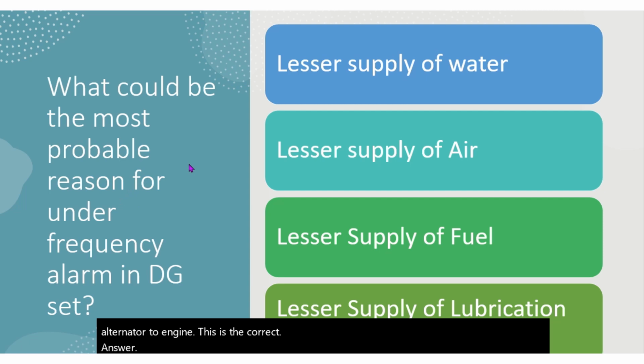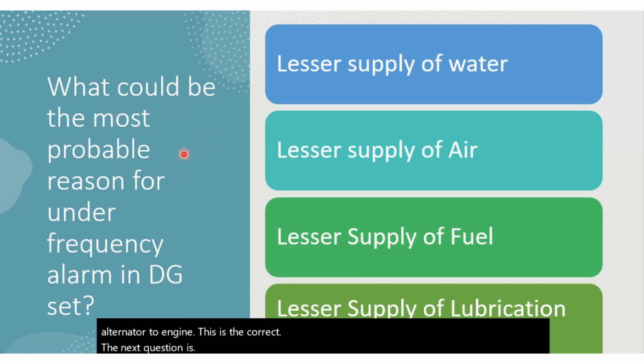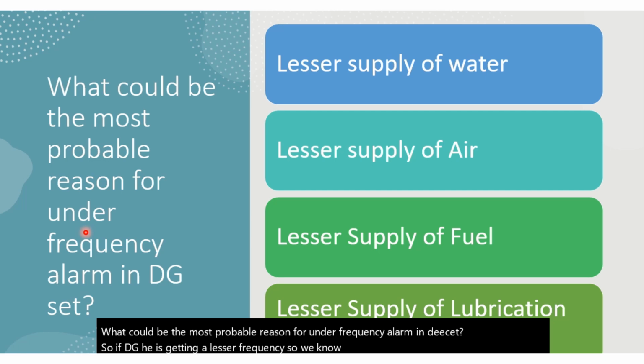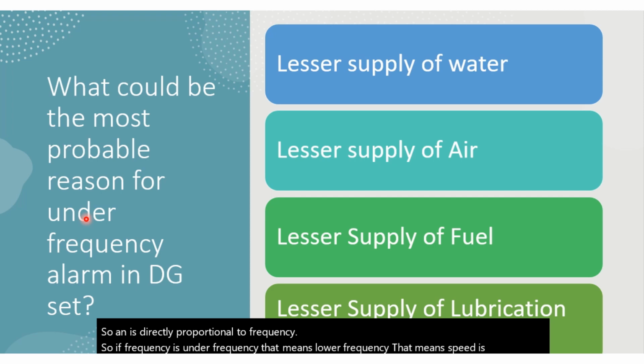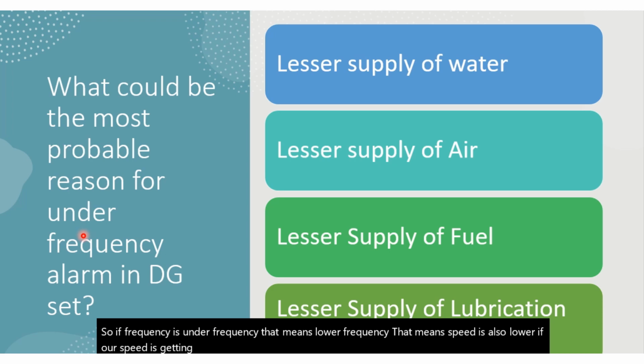The next question is, what could be the most probable reason for an under frequency alarm in a DG set? If the DG is getting a lesser frequency, we know there is a formula N equals 120 into F, where F is the frequency, divided by P, which is the number of poles. So N is directly proportional to frequency. If there is under frequency, that means lower frequency, which means the speed is also lower.